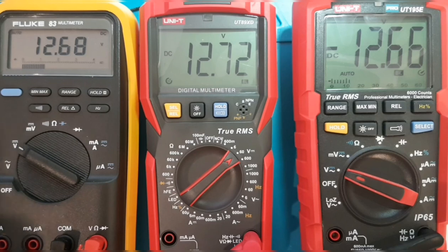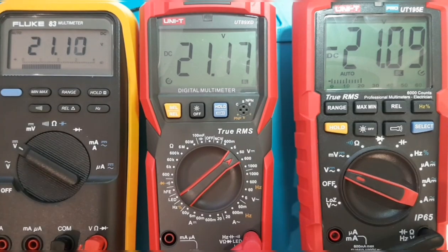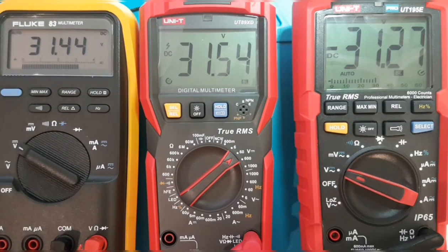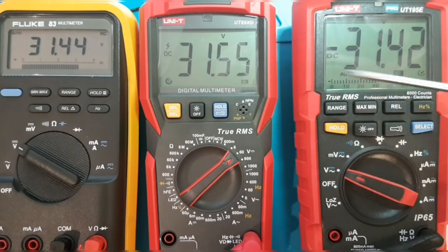The 195 Pro and Fluke 83 are pretty well neck and neck, the UT89XD just a tad higher. Going up to about 21 volts: 21.10 for the Fluke 83, 21.17 for the UT89, and 21.09 for the 195. Maxing it out at 31.3V: 31.44 for the Fluke 83, 31.55 for the UT89XD, and 31.42 for the 195E Pro.